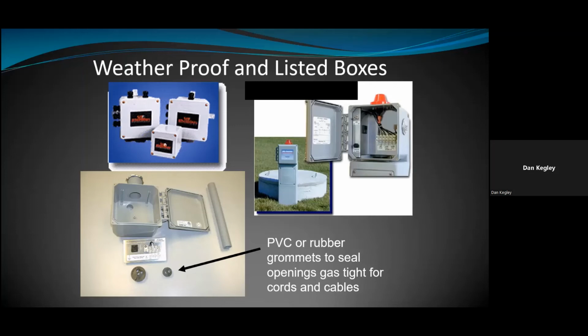Right. There's not a plug out there that I know of that can connect to the UF cable. As far as I know, the answer is no, because there are cord connector ends that go on the end of your cords. There's a female and male cord connector that can plug in together, but that cord connector is not listed for the UF wire. So you can't just connect that female cord connector on the end of your UF cable, because that's not what it's designed for. It may fit, it may work, but it's not UL listed for that connection point. Got it. That makes sense. And that's why it goes to a receptacle scenario for this particular case.